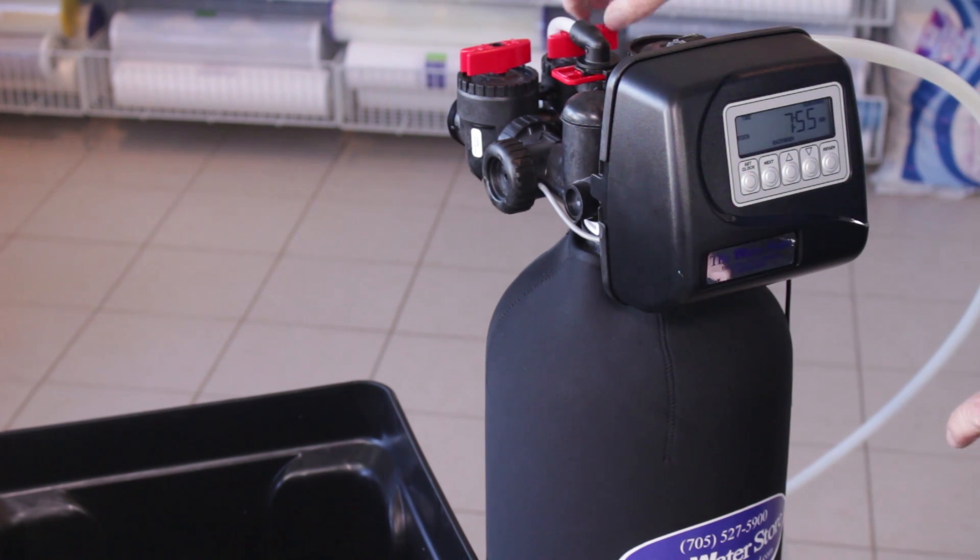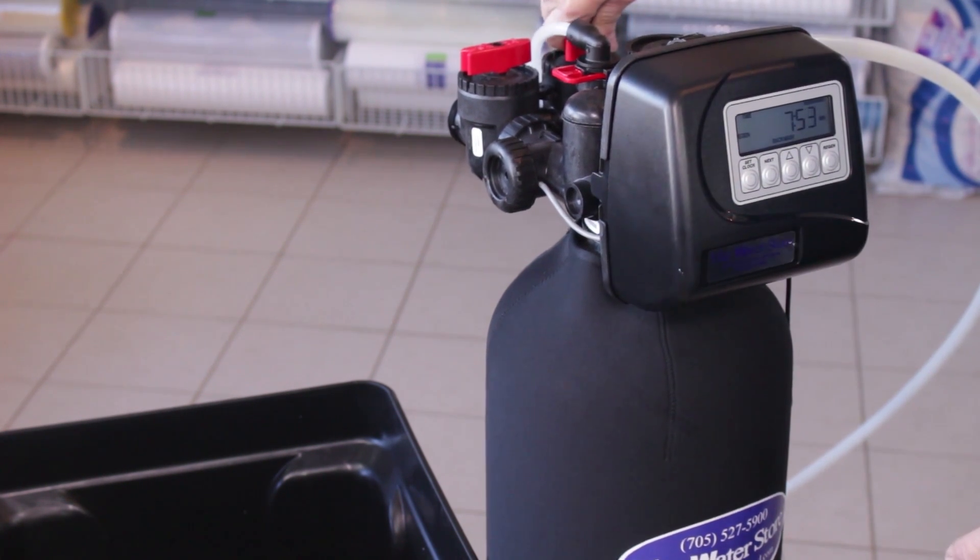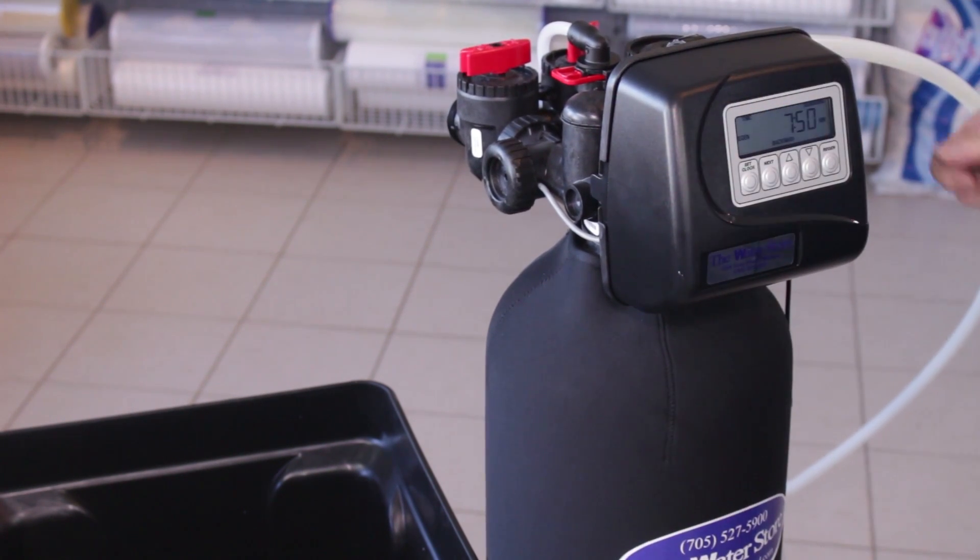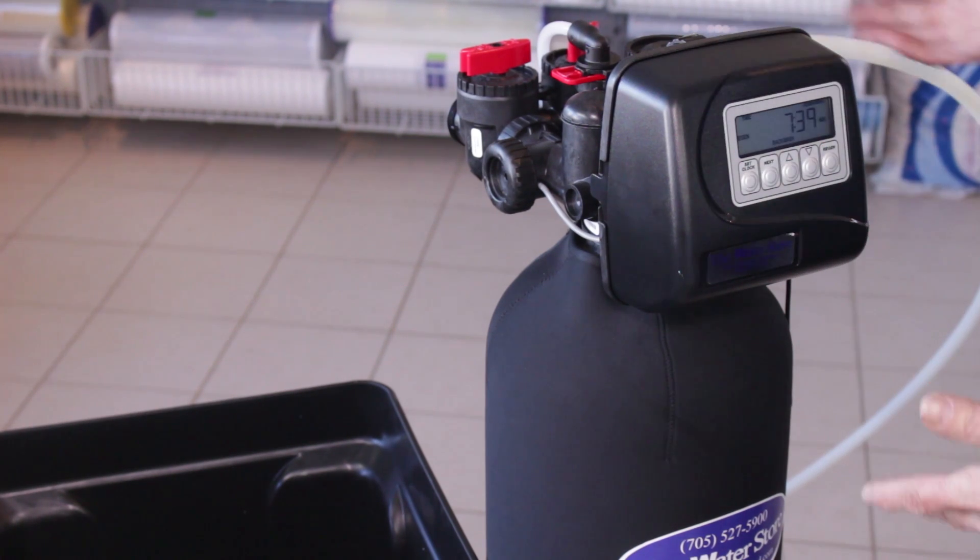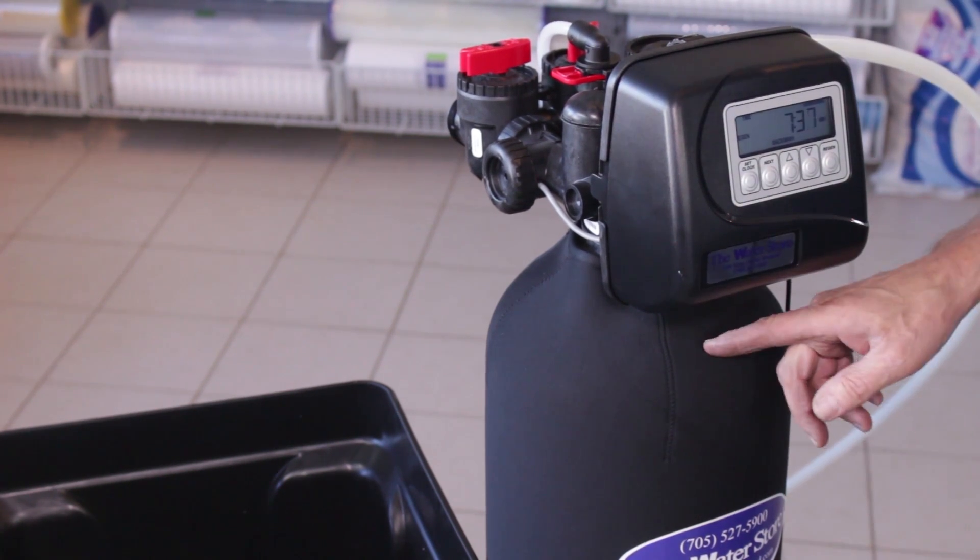So what we would do now is we'd open up the inlet valve until water starts to flow through and you'll see water now running to the drain. So what that's doing, well mostly air at first but then eventually you'll see water. What that's doing at this stage is it's flushing out all the air out of the media tank.